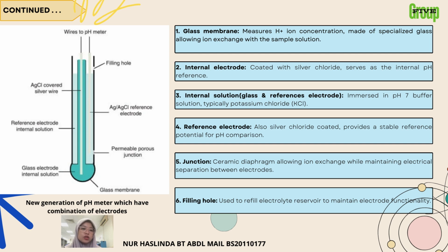The reference electrode, also coated with silver chloride, is included in this combination, designed to provide a stable reference potential for accurate pH comparison. A ceramic diaphragm, known as a junction, allows ion exchange while keeping the internal and external solutions electrically separated. Lastly, there's a filling hole used to refill the electrolyte reservoir, ensuring the electrode maintains its functionality over time. This integrated design simplifies the measurement process and enhances the accuracy and reliability of pH measurement.